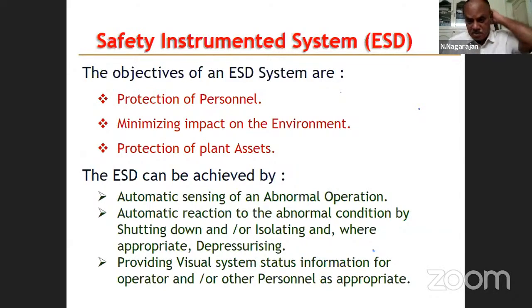Automatic reaction to the abnormal condition by shutting down or isolating, and where appropriate, depressuring. So once the system senses there is an abnormal condition, the sensors will send signals to the control system. Wherever there is a problem, you shut down and isolate that part, close the inlet and outlet valves. They are called shutdown valves. Close the inlet and outlet and isolate the equipment, and then take it for the next action.